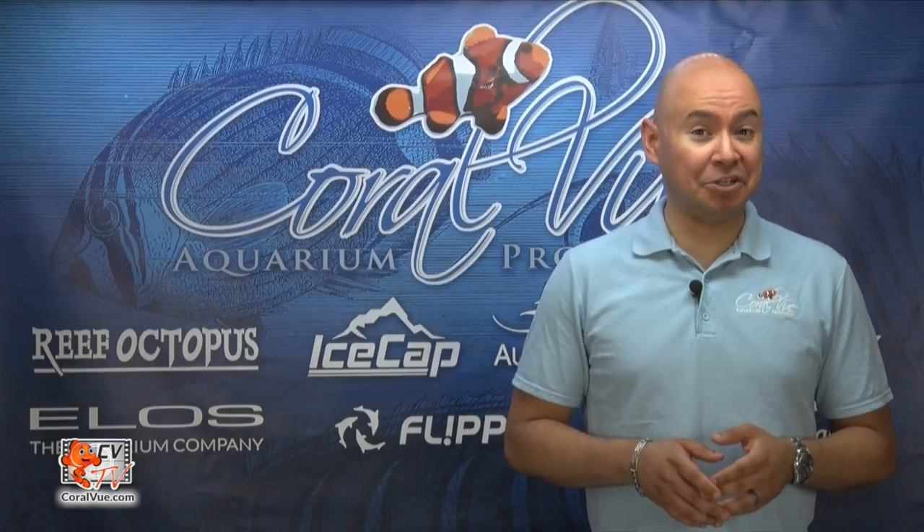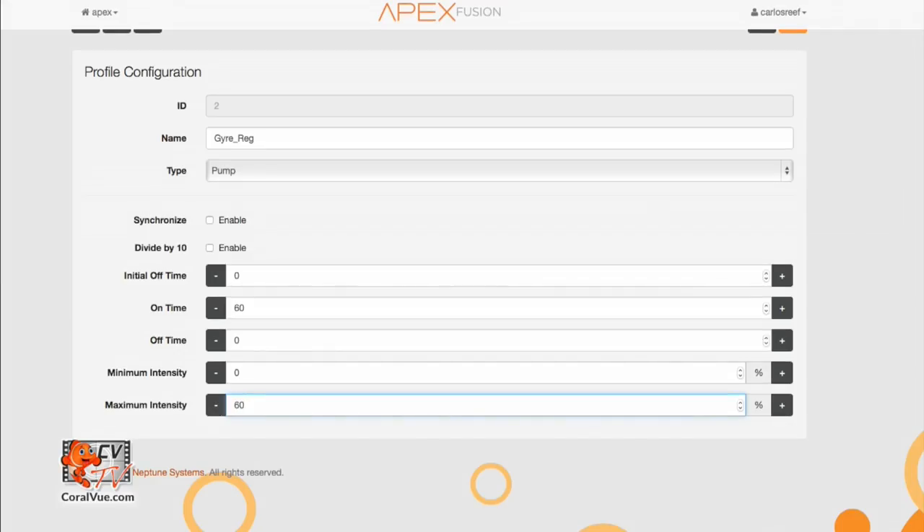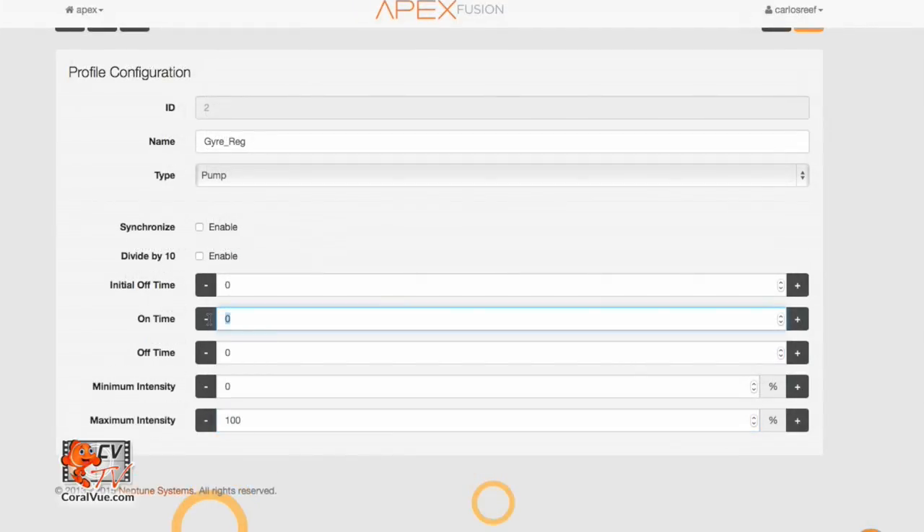What about changing the pulsing frequency of the Gyre? Say you want to program the Gyre to run at 60% for one minute and then run at 20% for 30 seconds. Or program the pump to run at 100% for 15 seconds and then run at 50% for two minutes. It can all be done programming it on your system controller.